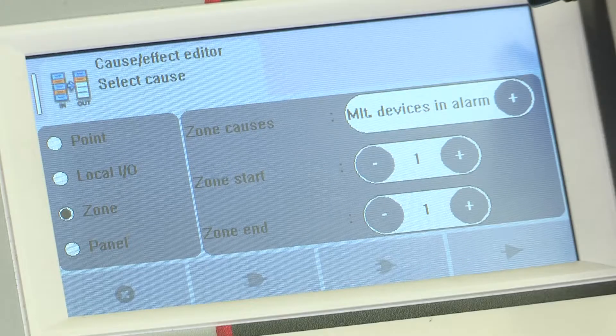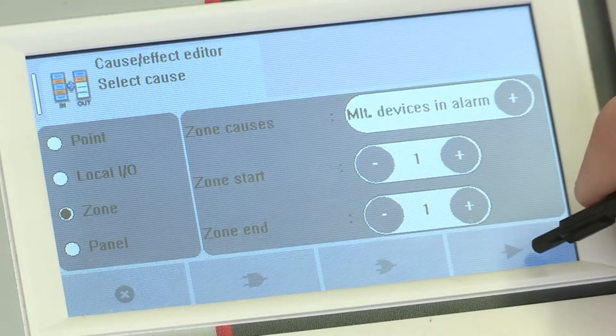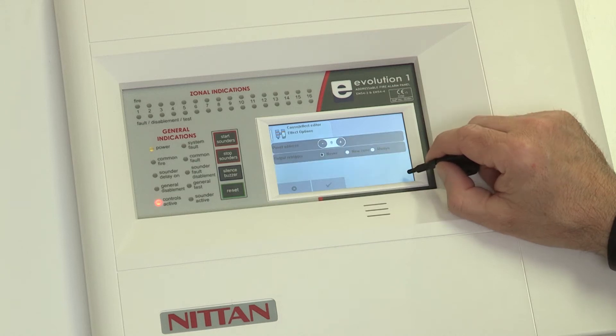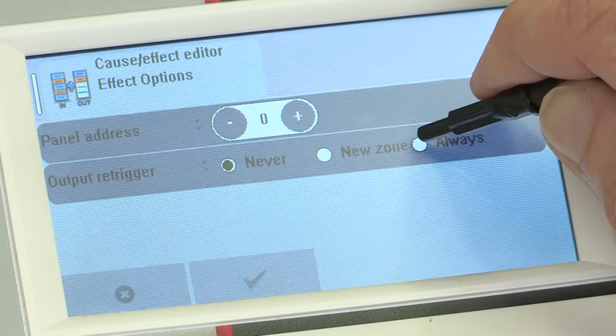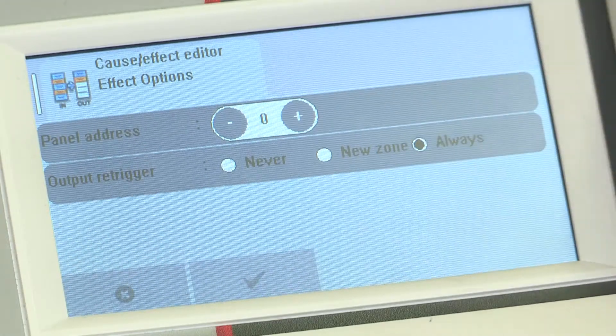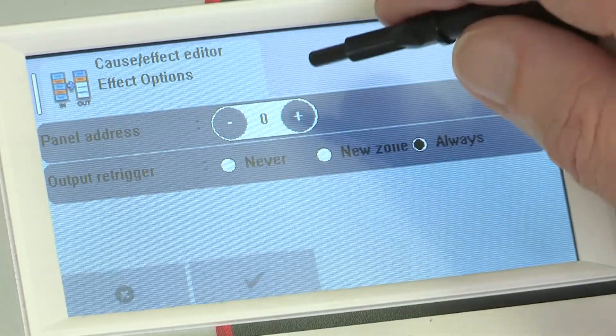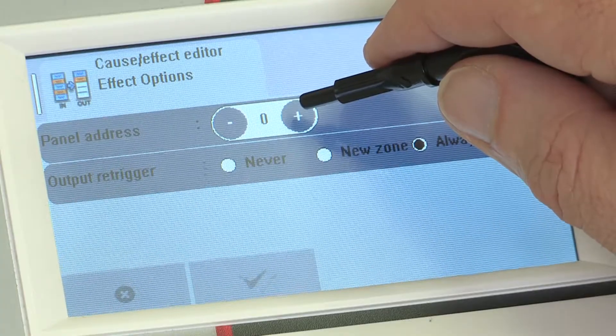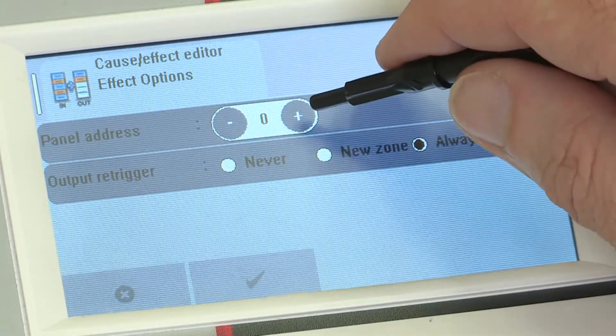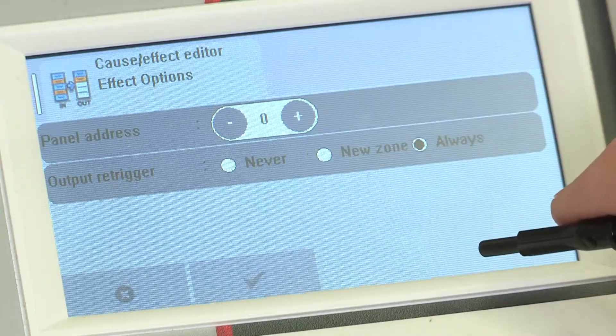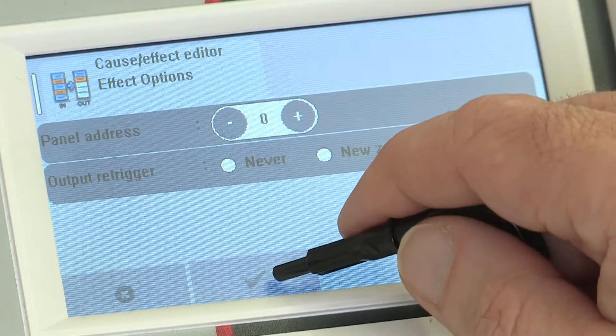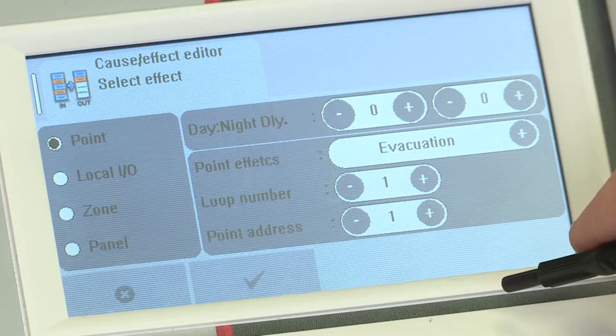When you have completed this section, click on the triangle symbol at the bottom right to move to the next screen. For re-triggering, we recommend always choose 'always'. Panel address is used for setting an effect rule on another panel on the network — if this is a standalone panel, leave it as zero. Click on the tick symbol at the bottom of the screen to move to the next.